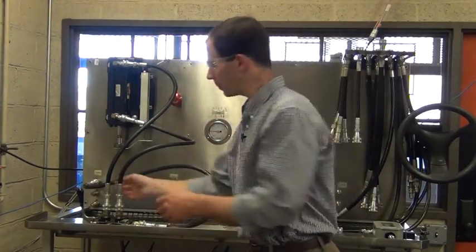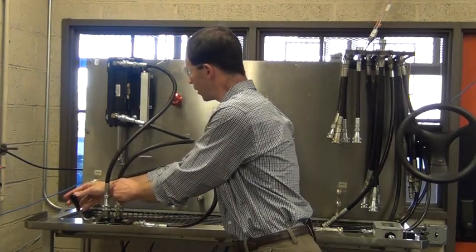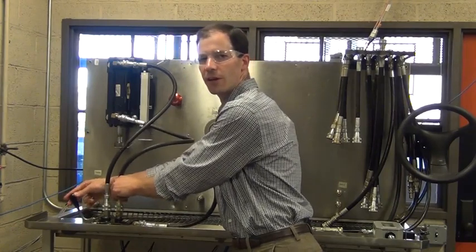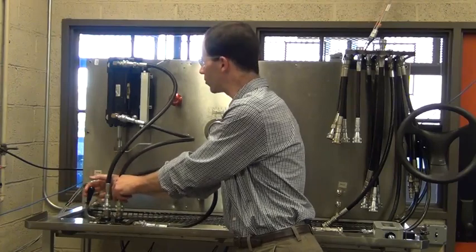Now you can hear the pump running and I'm going to cycle the valve. You can see how it's extending and retracting. You'll note that there's a slight difference in the velocity that it extends versus retracts, and this is due to the difference in the cap and the rod side areas.